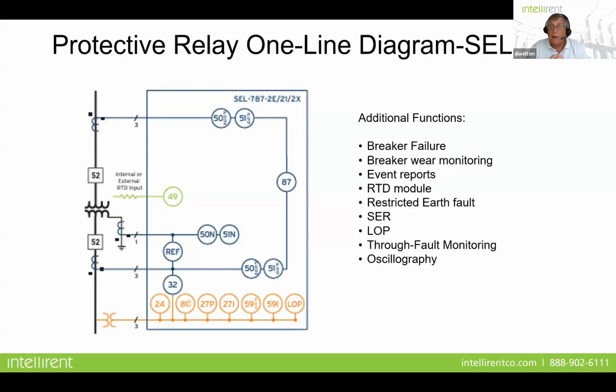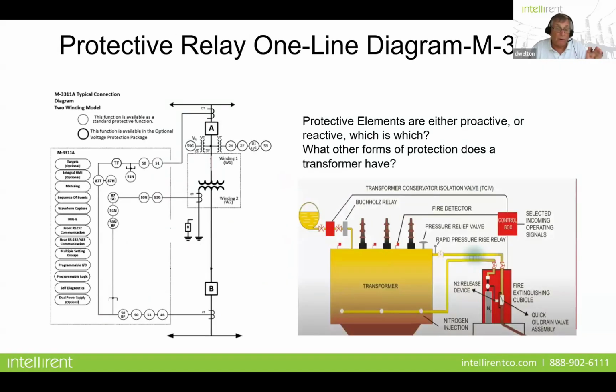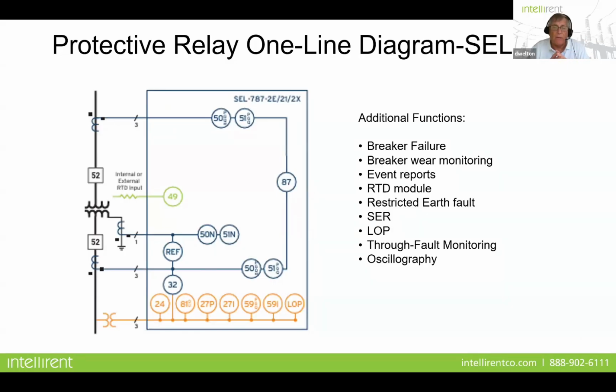So here's a one-line diagram from a Schweitzer relay, and there are some things I want to point out here. You'll see between the two, they're fairly similar. They're diagrammed out a little bit differently, but the elements are pretty much the same. You have your two sets of CTs, and you have your differential relay monitoring the currents on both sides of the transformer, and then you have some of your voltage and some of your overcurrent relays that are those proactive. But there are some things in a transformer relay that are very, very important to be aware of.